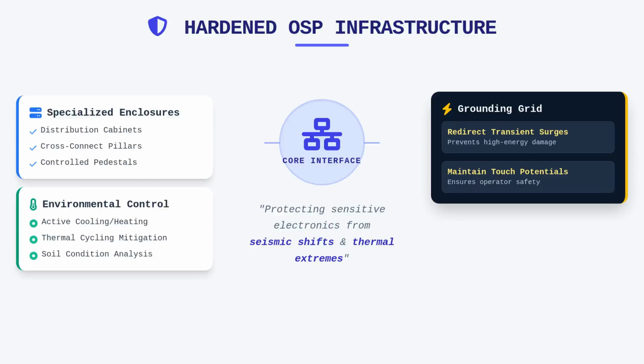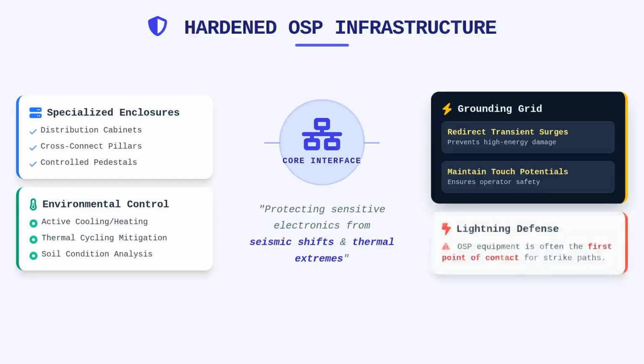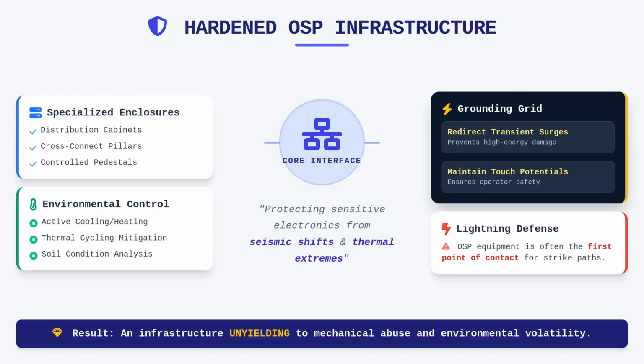This grid, consisting of grounding electrodes and bonding conductors, must be robust enough to handle high-energy events, as OSP equipment is often the first point of contact for lightning-related strike paths. By meticulously selecting these hardened components, we create an infrastructure that remains unyielding in the face of mechanical abuse and environmental volatility.